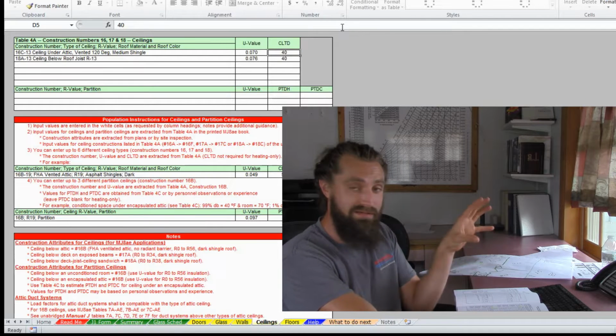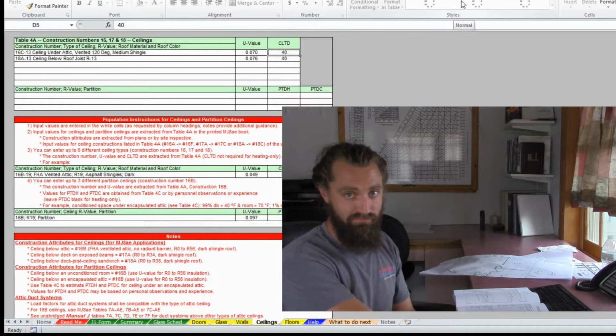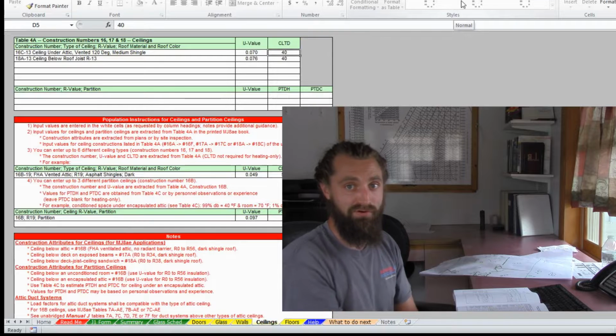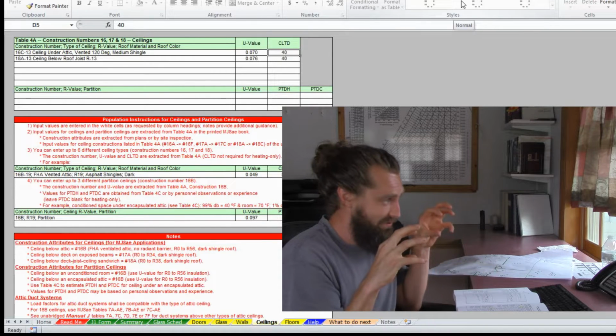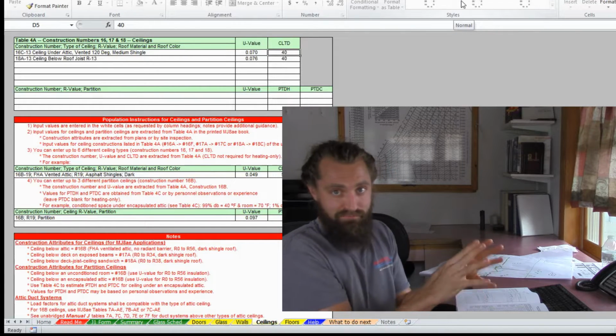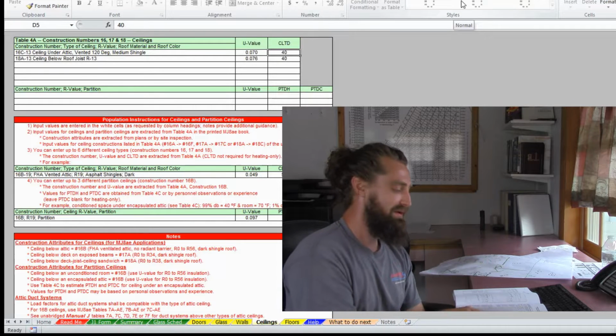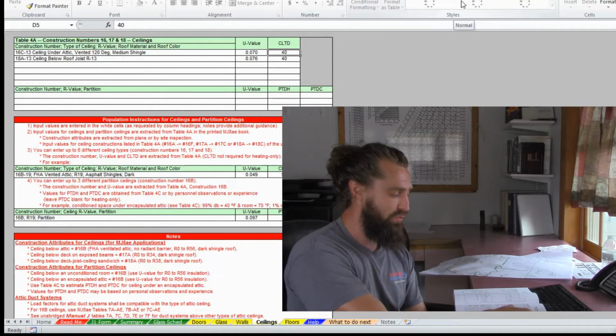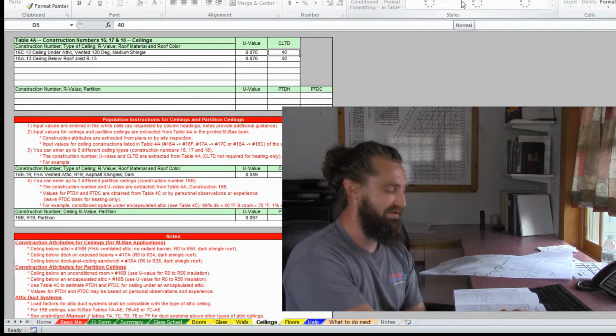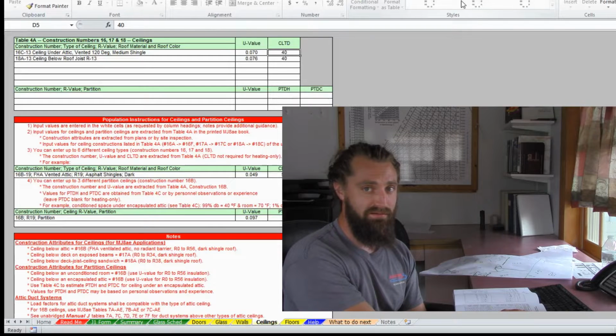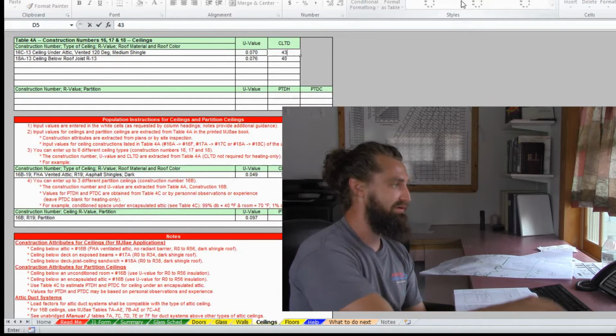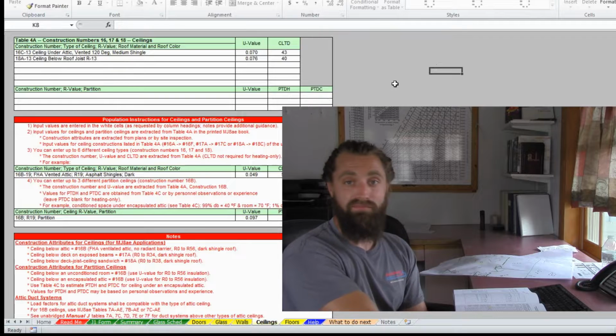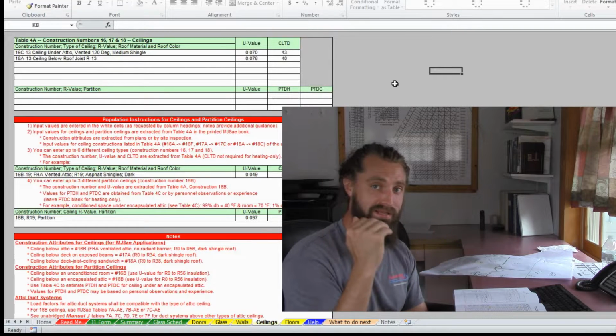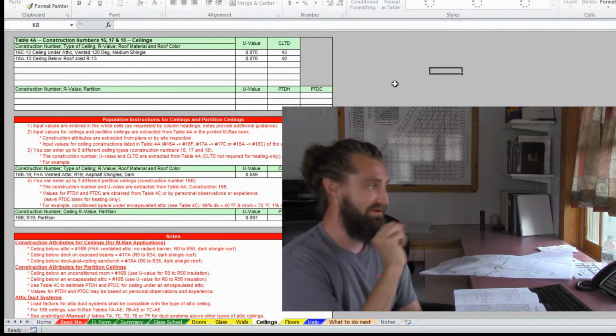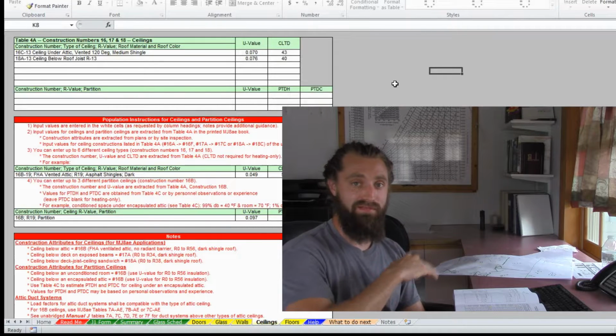And the nice thing with this spreadsheet is, unlike a program where if you tell it where you're working it just plugs in its own numbers, I could fudge these a little bit. The book says for a 20 degree temperature difference and a daily range of medium, we could use 40. Let's just say that I wanted to put 43 instead. I could put 43 in here, okay? And then it would size all of our heat transmission through that ceiling based on a cooling design temperature differential of 43.